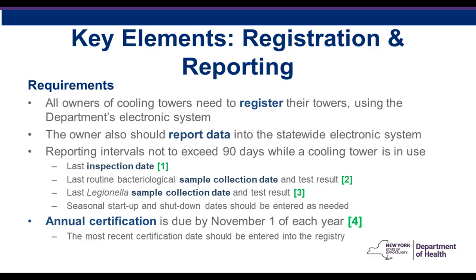So the first thing we'll cover is the section on cooling towers. The key elements: all cooling tower owners are required to register their towers in the statewide registry and to update their sampling, inspection, and certification information at intervals not to exceed 90 days while the tower is in use. So if a tower has been entered into the registry but the sampling or other information is out of date, the tower is considered to be non-compliant, and enforcement actions may be taken against the owner.